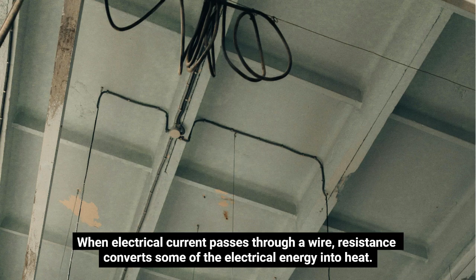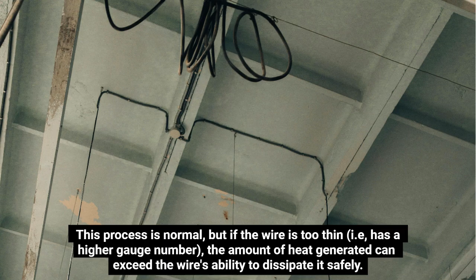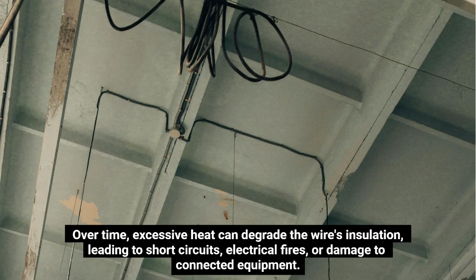When electrical current passes through a wire, resistance converts some of the electrical energy into heat. This process is normal, but if the wire is too thin, i.e., has a higher gauge number, the amount of heat generated can exceed the wire's ability to dissipate it safely. Over time, excessive heat can degrade the wire's insulation, leading to short circuits, electrical fires, or damage to connected equipment.